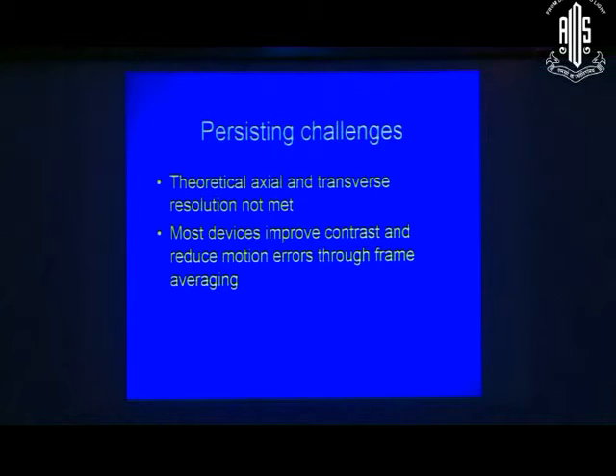There are still challenges with the OCT. And one is, even though it is supposed to give you a brilliant resolution, you don't actually achieve those values. Partly because there is some averaging that happens in order to eliminate motion artifacts and other things. So you think you're getting a 5 micron axial resolution or transverse resolution. Those are actually not the values you get. You get something which is lower than that on an image.